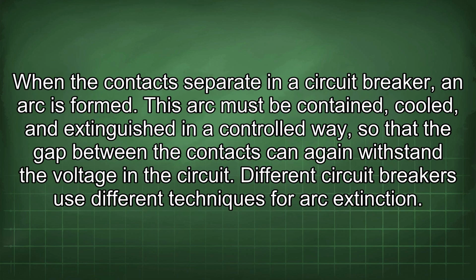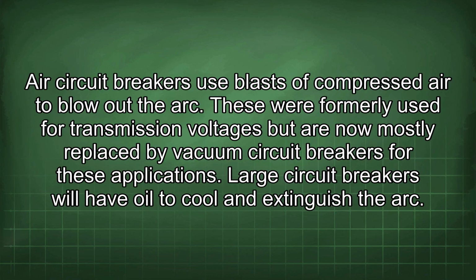When the contacts separate in a circuit breaker, an arc is formed. This arc must be contained, cooled, and extinguished in a controlled way, so that the gap between the contacts can again withstand the voltage in the circuit. Different circuit breakers use different techniques for arc extinction. Air circuit breakers use blasts of compressed air to blow out the arc. These were formerly used for transmission voltages but are now mostly replaced by vacuum circuit breakers for these applications.